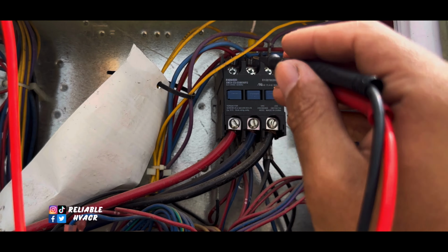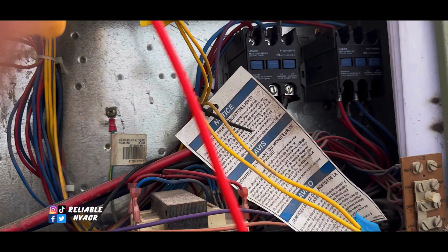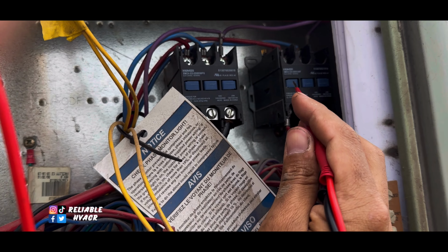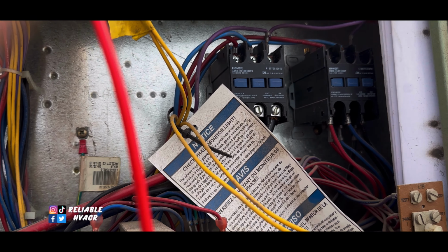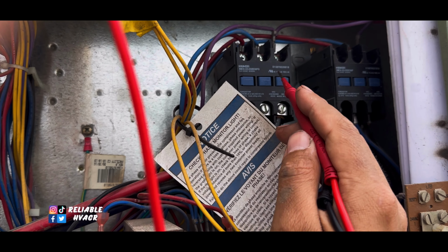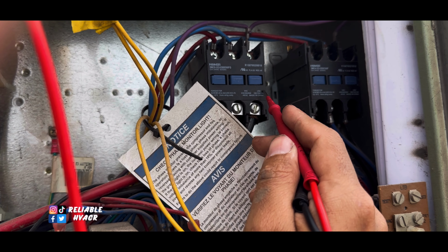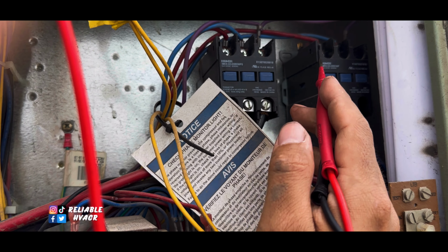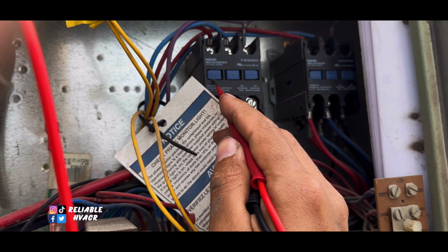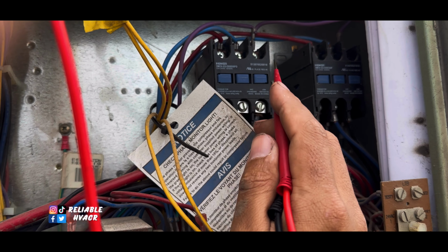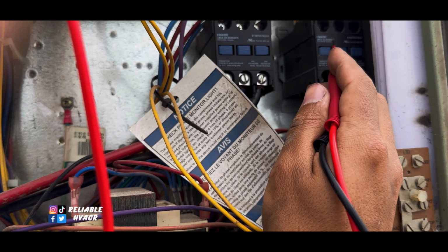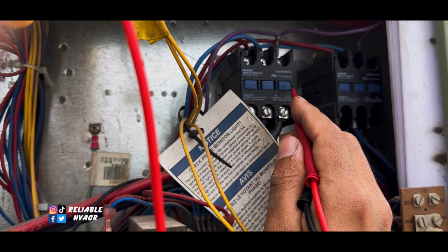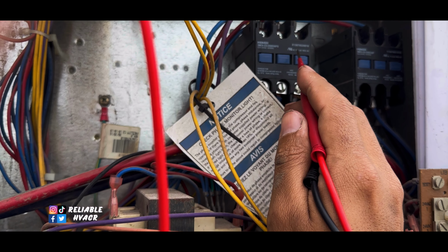Now we're going to check our contactor. I'll check the coil. Okay, these were about 5 to 6 ohms, which is okay on a 3-phase 30 to 40 amp contactor. If you guys are doing the 2-pole, those are a little different, those are closer to 12, 13. These I usually get on a new one like 7 on the ones I use. This one's 5 to 6.